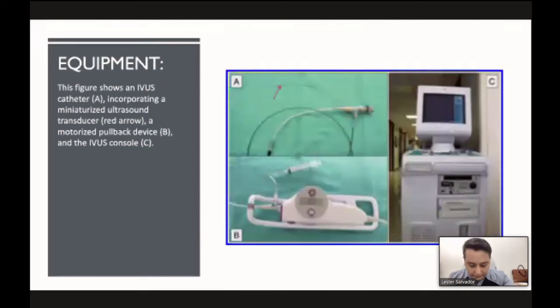So what is the equipment used in IVUS? Just to familiarize anyone who is seeing one for the first time. First, we use an intracoronary ultrasound catheter. Usually they have an outer diameter of around 2.6 to 3.5 French. These are very small devices that are suitable for examination of more distal coronary locations, and they permit examination of almost all stenotic segments prior to intervention. The smallest catheters can be placed through a large lumen 6 French guide, although some prefer to use a 7 or 8 French.